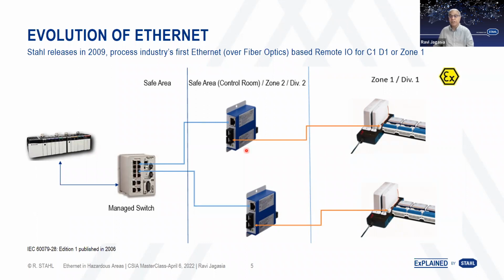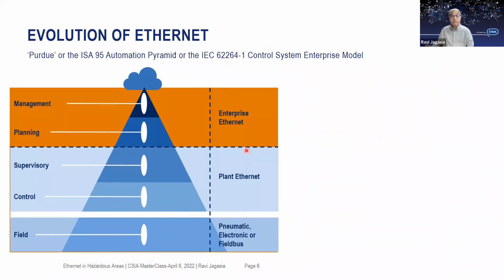With fiber optics, multi-mode and single mode, you could travel the distance you wanted, and you could still manage remotely installed IOs from the control room. Going forward, we have the Purdue ISA 95. And in Purdue ISA 95, we know that from the field to the control room, we use the 4 to 20 milliamps, or the 4 to 20 milliamps with HART or smart transmitters. And then we definitely have the discrete signals.